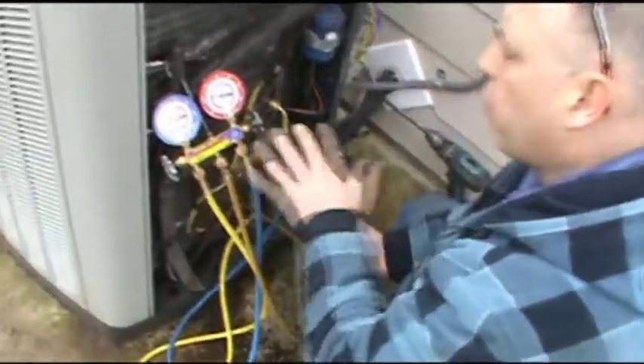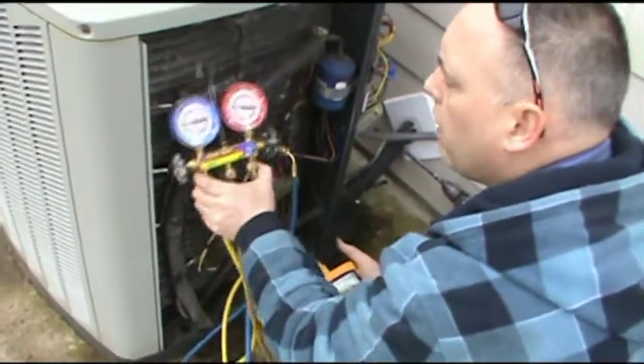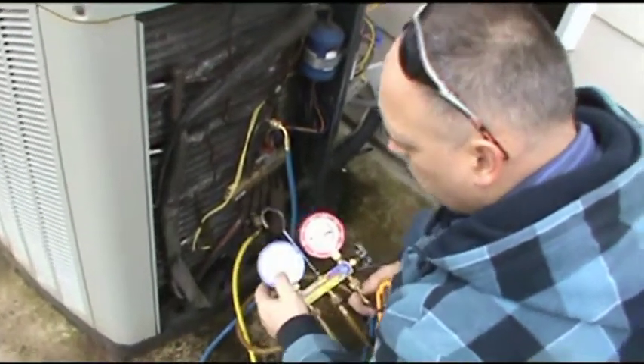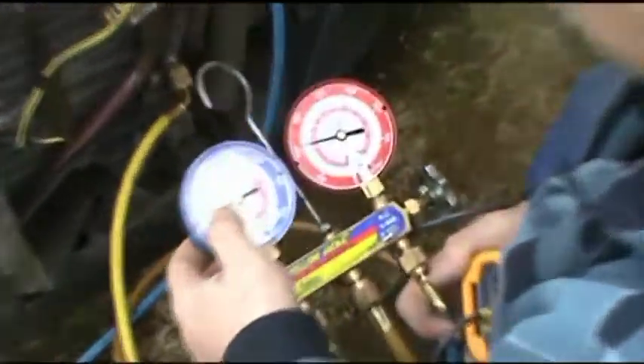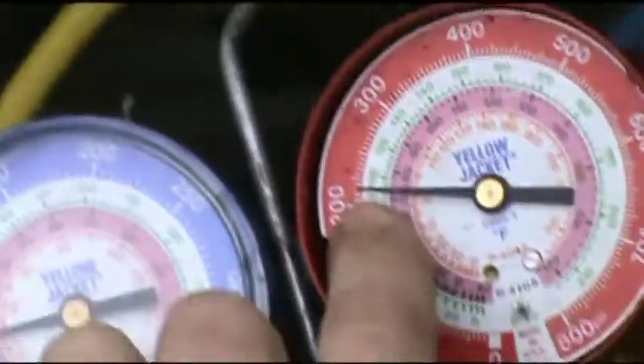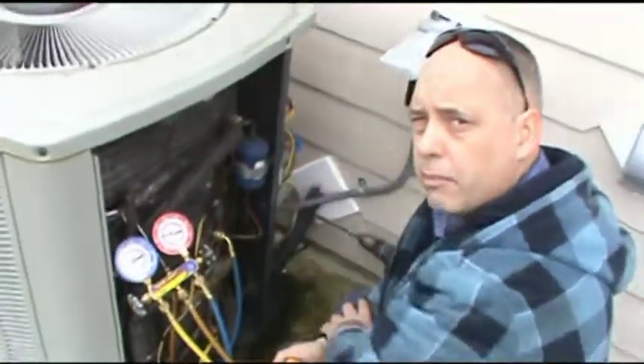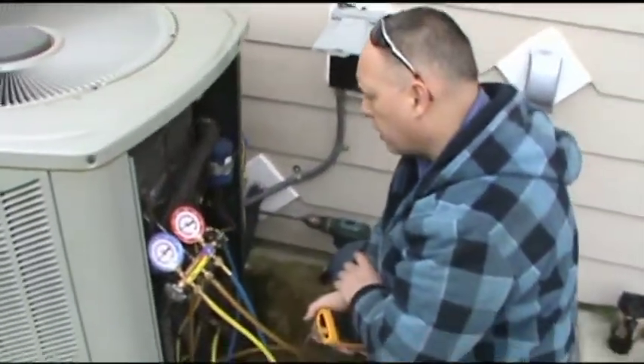We're going to take a look at our pressures now that the machine's been running for 5 minutes or so. And you can see a suction pressure of 60, which is about right for this outside air temperature. And then we have a high side or head pressure of about 215, which is again about right based on the temperature inside the home of 69 degrees.